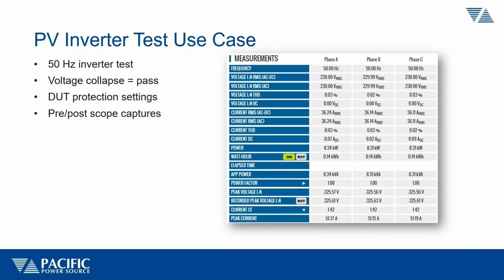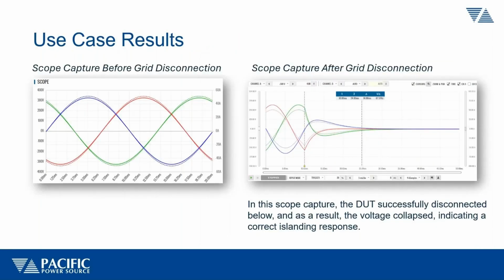This is an example of the built-in web browser function, Smart Source, that will allow you to monitor the output of the grid simulator. A similar screen is available for the load. It'll show you the voltage and current on all phases and the frequency, as well as the power and the reactive power. And it also includes the scope capability. In this case, on the left, you see the steady state condition before the test. And on the right-hand side, you will see the effect of disconnecting the grid power. You see the time measurement of how long it took for the DER to disengage and basically the voltage to drop to zero. So it's very convenient to have all that integrated into your test equipment.